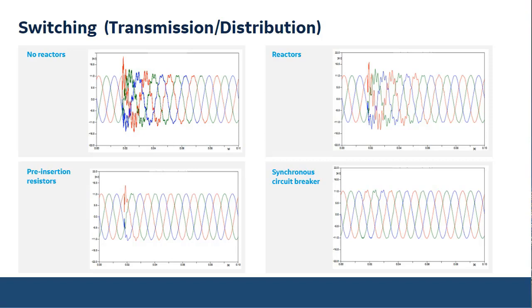What I'm trying to show here is that not having reactors in a cap bank may be an issue for the switching device and actually also for the cap bank. So the reactors are added to limit the I0 and the f0, the initial frequency of the transient. But there is just a limit on how much it can limit. The resistors do limit it further than the reactors, but of course the price can be prohibitive, and the same for a synchronous circuit breaker. So the big question here is how much you want to spend to limit the cap banks and switching devices to the limits that they can withstand. We may be talking about some thousands of dollars, tens of thousands of dollars, or maybe hundreds of thousands of dollars, depending on the solution.